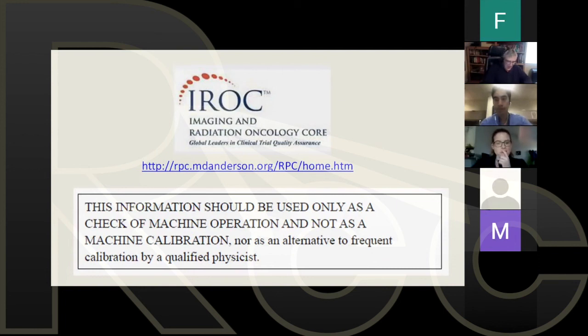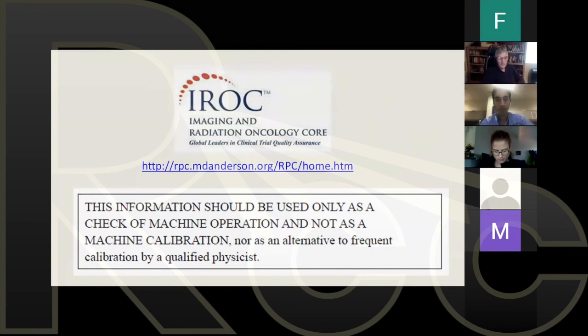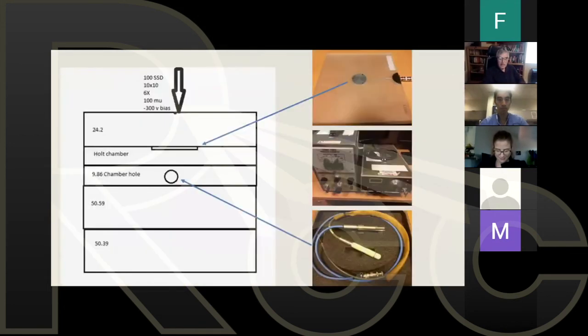Okay. Well, that could be a very long answer. There are many errors that you can make in the use of an ionization chamber. And it starts with the correct temperature and pressure. Are you using the correct temperature and pressure to correct your reading? Because the chambers that we use, all of them, to my knowledge, communicate with the outside air, with the air in the room. And the readings that you get will vary from day to day, sometimes up to 2%, depending upon temperature and pressure. So you must correct your reading with temperature and pressure.